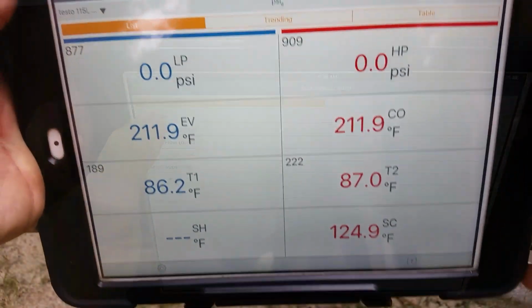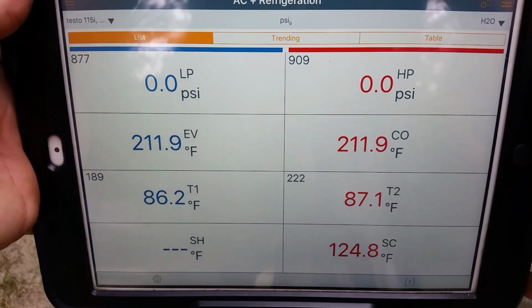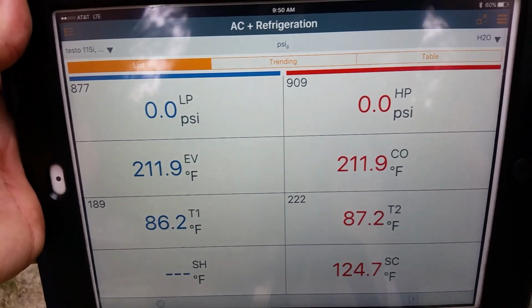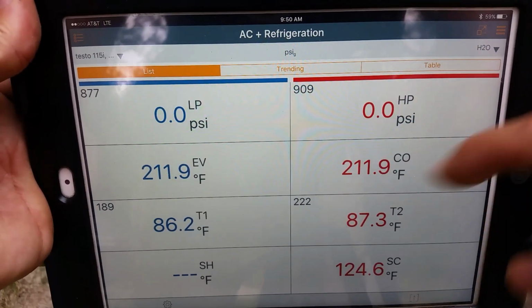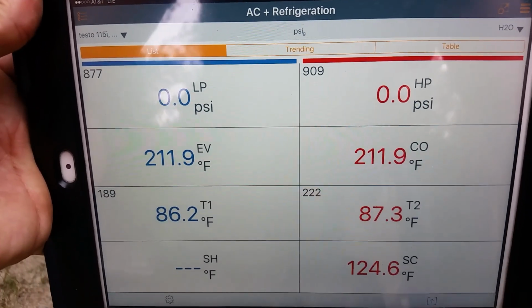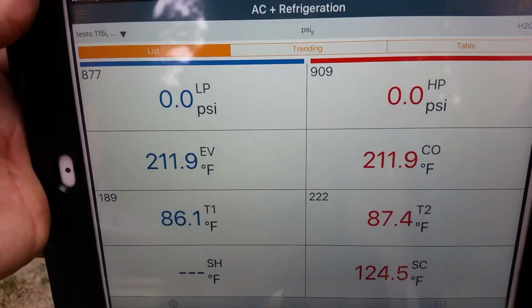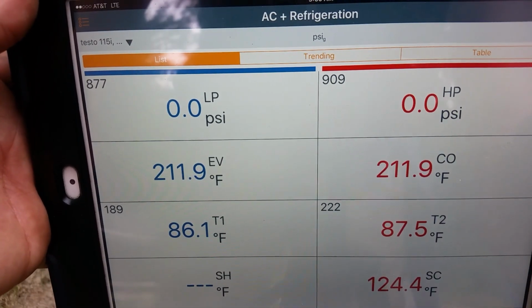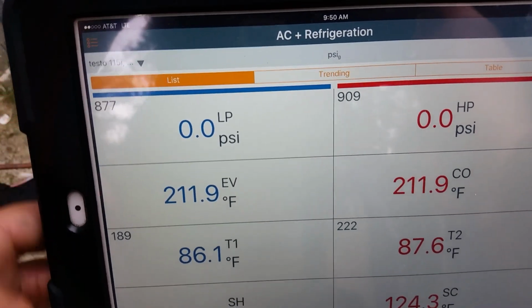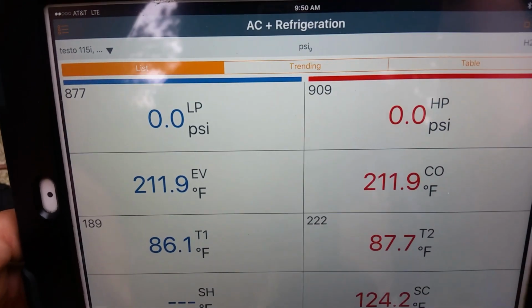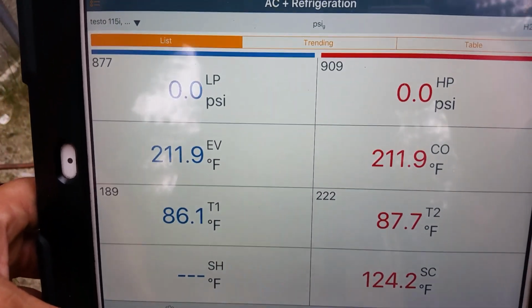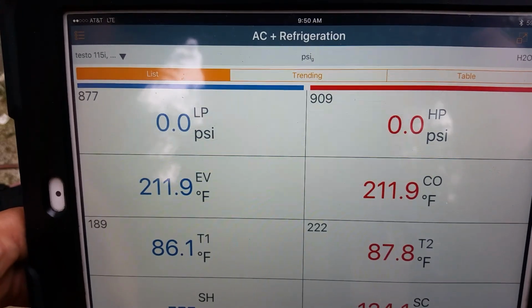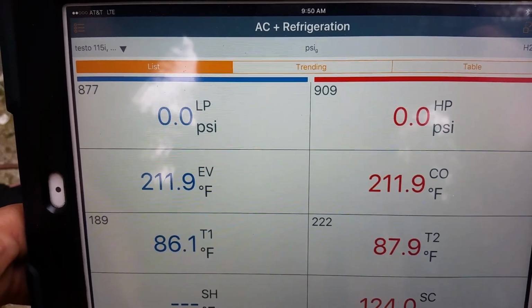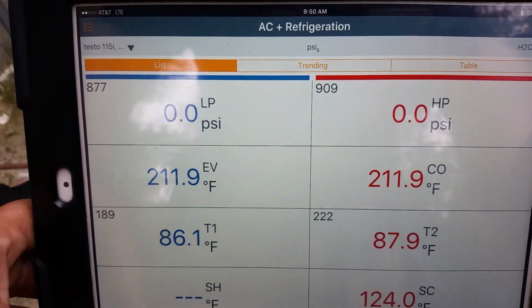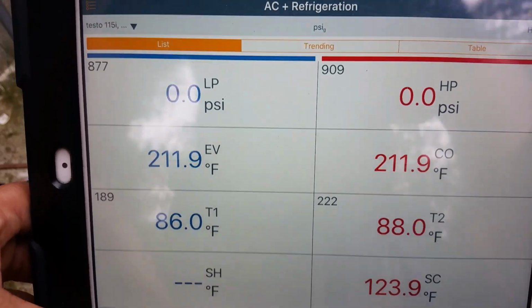Alright, so we got our app, we got everything set up, all of our probes are linked in, and as you can see right now our pressures are at 0. You want to make sure, because these probes are not temperature compensated, that when you turn them on they are zeroed. If they happen to be off in the negative or positive, that's normal, don't be discouraged, it's just because they don't compensate for temperature. So if they're in a hot or cold vehicle or climate, the pressures can change a little bit.